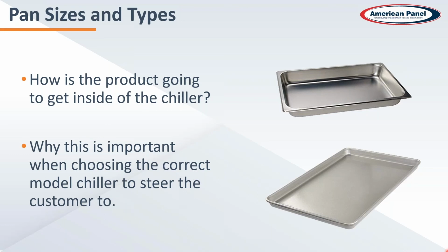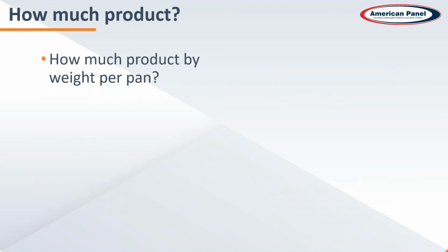Next, we got to talk about how much product is going in that pan by weight. Another sizing factor of our blast chillers has to do with the weight capacity, because what we're trying to do is pull those BTUs out of the product. So the refrigeration systems are designed just like any other refrigeration system. You got to remove BTUs. You got to take the hot out and make it cold. So you have to size it appropriately.